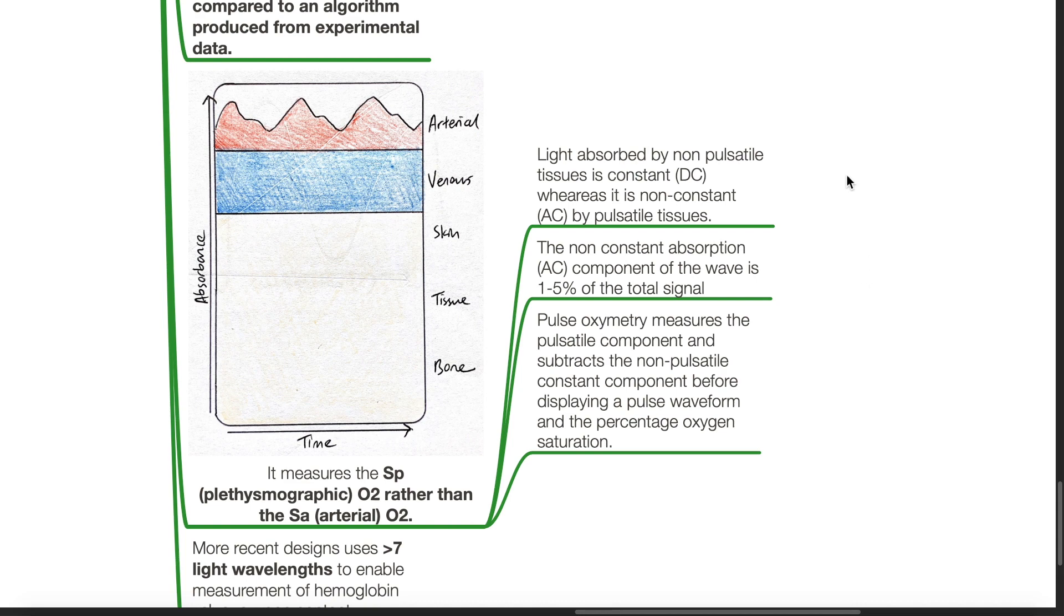As light absorbed by non-pulsatile tissue is constant, whereas it is non-constant by pulsatile tissues, the non-constant absorption component of the wave is 1 to 5% of the total signal. Pulse oximetry measures the pulsatile component and subtracts the non-pulsatile constant component before displaying a pulse waveform and the percentage oxygen saturation.